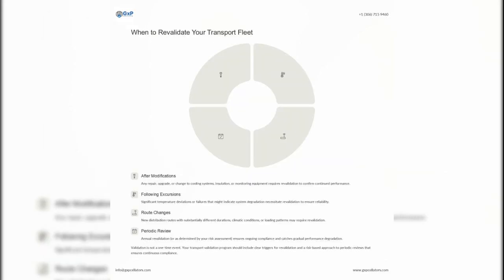Revalidation of your transport fleet is necessary after modifications, following excursions, and during route changes. Any repair, upgrade, or change to cooling systems, insulation, or monitoring equipment requires revalidation to confirm continued performance. Significant temperature deviations or failures that might impact system degradation necessitate revalidation to ensure reliability. New distribution routes with substantially different durations, climatic conditions, or loading patterns may require revalidation.